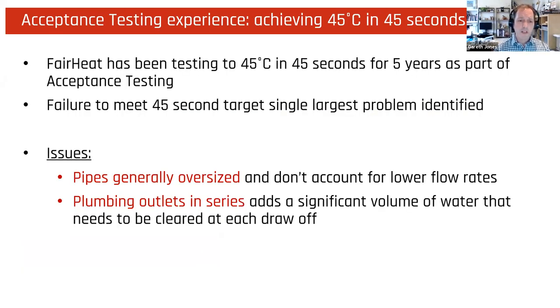We've been doing acceptance testing, so we pioneered acceptance testing. It's great to see that that's now in CP1 2020. We've been doing it for 5 years. We've actually been doing the testing of 45 degrees within 45 seconds for 5 years now.